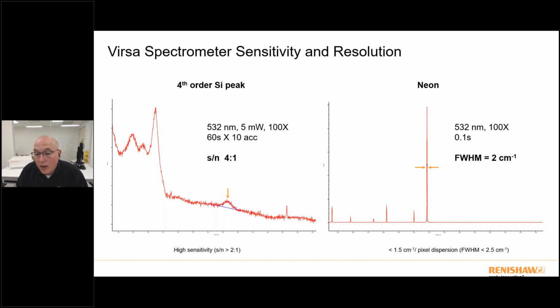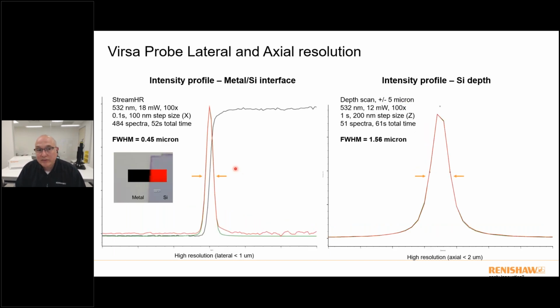In terms of spectral resolution, our spec is full width half max on a neon peak of 2.5. In this case, I actually measured 2 wave numbers on the system behind me. We also have a 1.5 wave number dispersion based off of whatever laser source you're choosing, so we can select the appropriate grating laser combination. So in terms of sensitivity and spectral resolution, we're definitely there. The big advantage, I think, is the resolution that you get spatially. You don't see this on fiber-based instruments. We have a lateral resolution which is less than 1 micron. And in this case, we went from doing a fast streamline HR map where we collected, I think, about 500 spectra pretty rapidly.